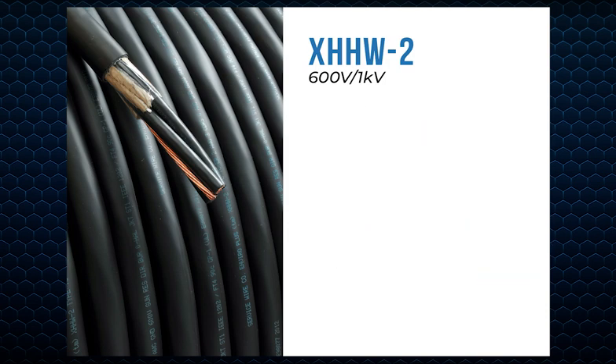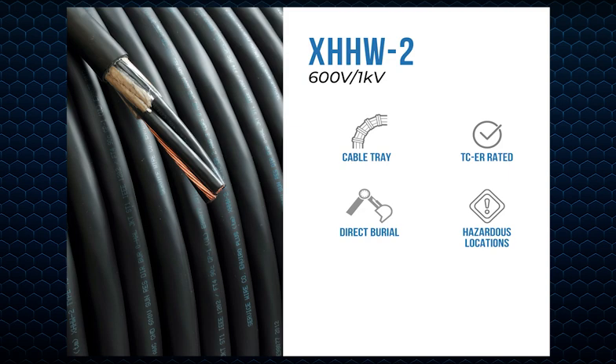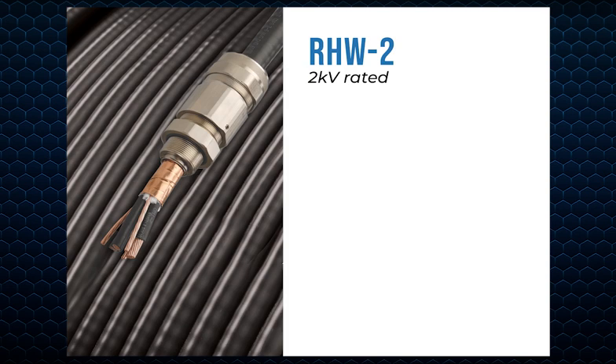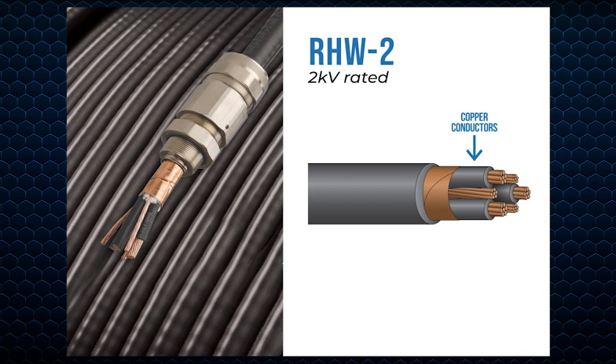Service Wire's XHHW-2 can be used in cable tray, TCER rated or direct burial applications, and hazardous locations designated as Class 1 Div 2 or Class 2 Div 2. Service Wire offers 2 kV rated RHW-2 for variable frequency drive applications. It is available in 14 gauge through 750 kcmil. The cable consists of 3 stranded copper conductors insulated with heat and moisture resistant XLPE, phase identified and cabled together with 3 symmetrical bare copper grounds. The cable core is covered with a copper tape shield and overall black PVC jacket.